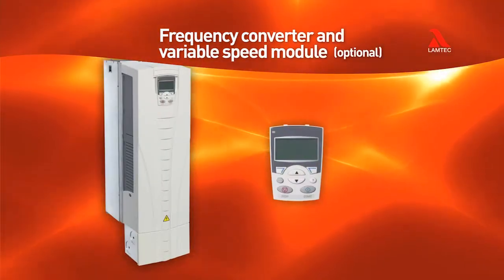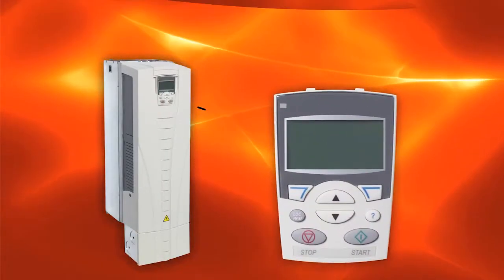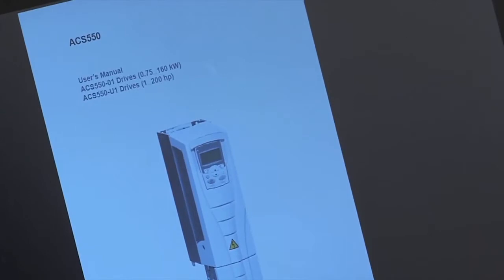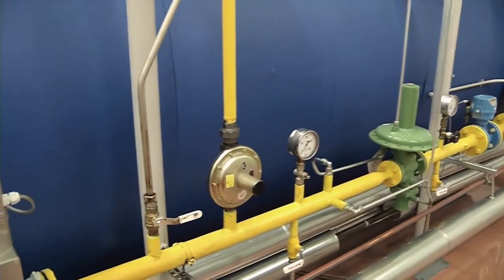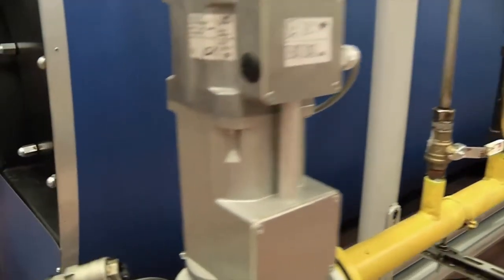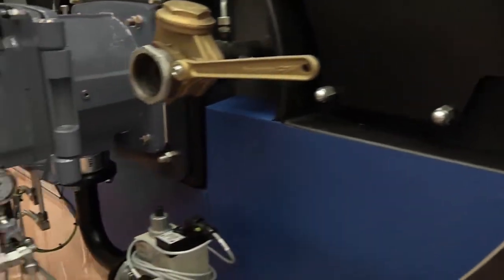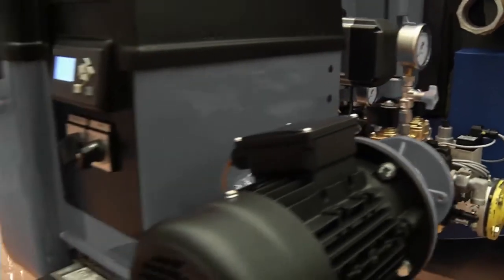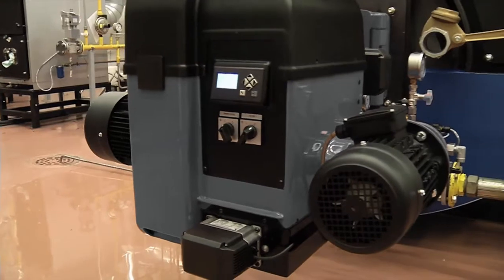The frequency converter parameters must be set for the fan motor control. Refer to the manufacturer's manual. The settings you need to change are the acceleration and deceleration time and maximum and minimum frequencies. You can find detailed instructions in the burner manual.